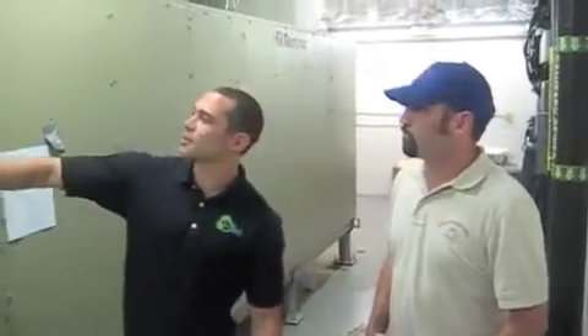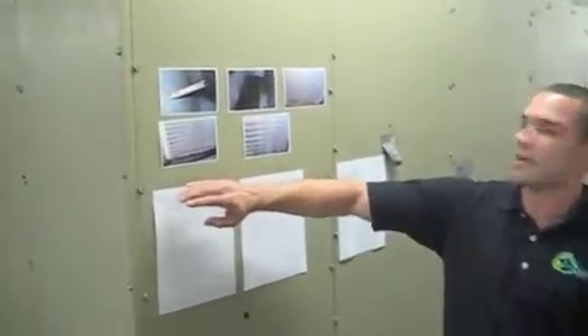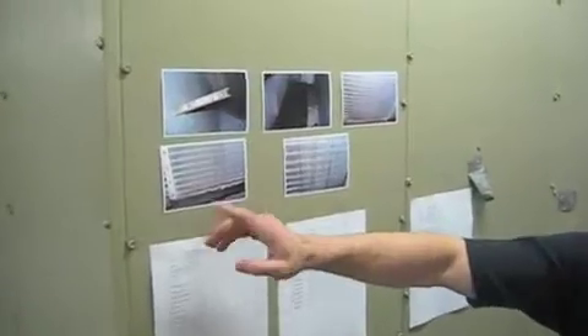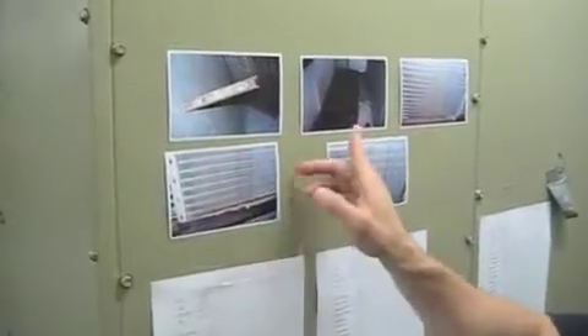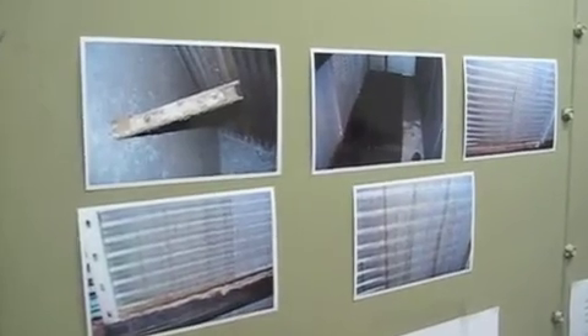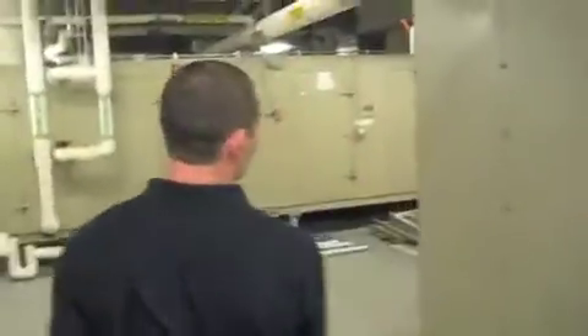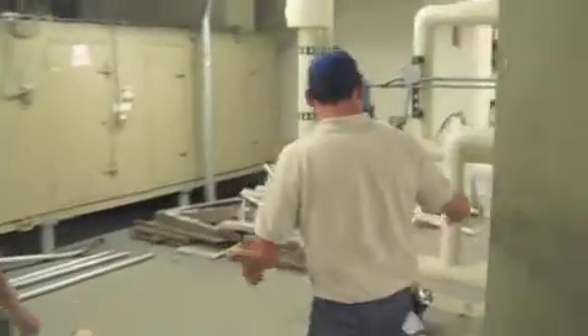If we can see a picture of this system over here — this is about a month and a half ago. You can see all this gunk all over the evaporator coils, stuff basically making the evaporator coils function inefficiently, costing the hospital more money. So let's jump on over here — this is a month and a half after those pictures were taken. Wes, show us what we've got here.